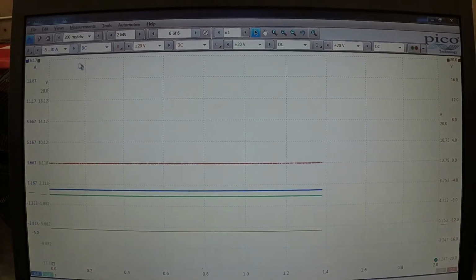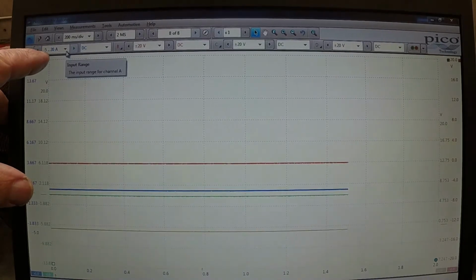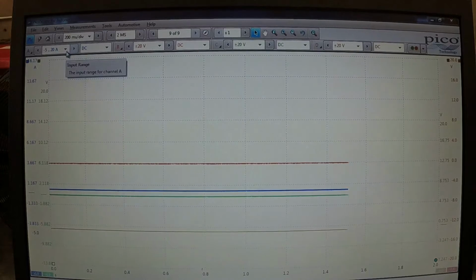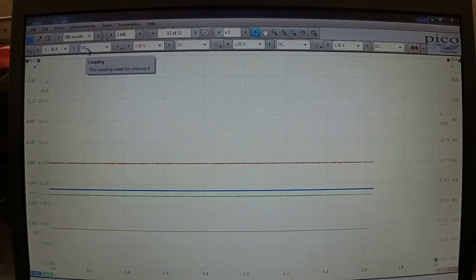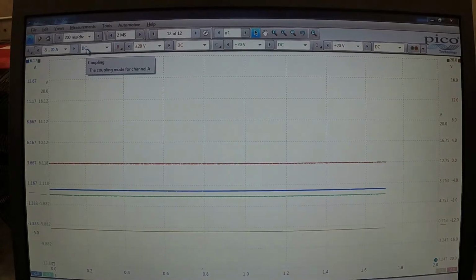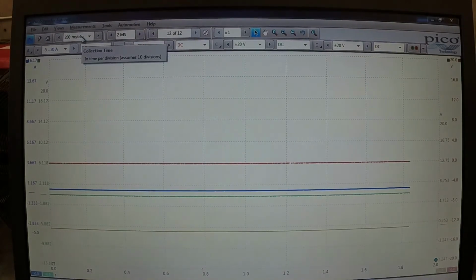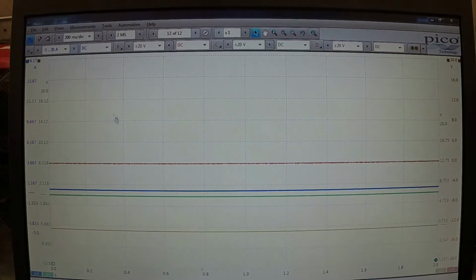Now I'll go up here, and if you notice my settings, it's set to capture from -5 to 20 amps, so it'll capture both the bottom side and the top side of the signal. I'm in DC coupling, which is what we normally use, and we're at 200 milliseconds. We might change that depending on what kind of signal we get - we can increase or decrease it depending on the size of our signal so we can see it better.